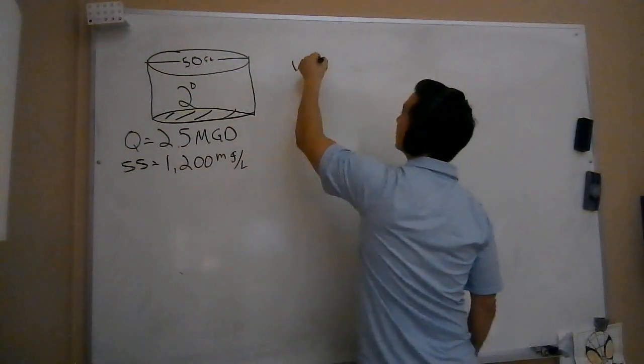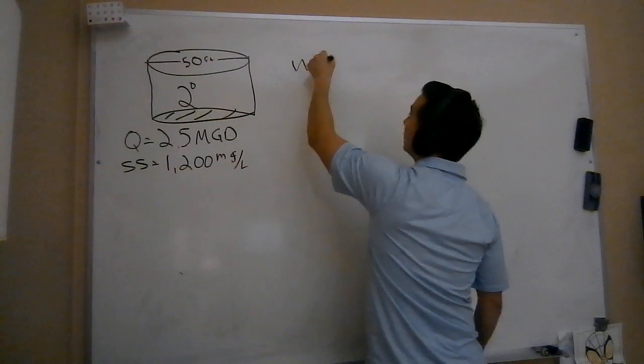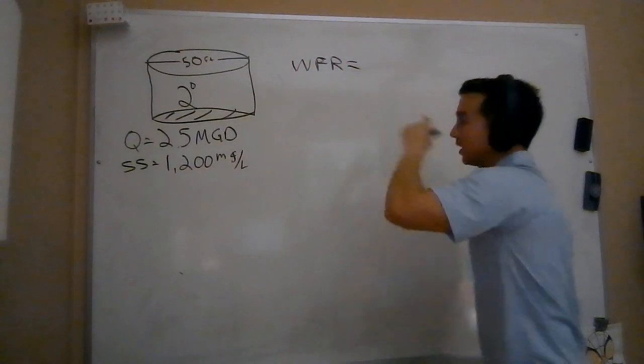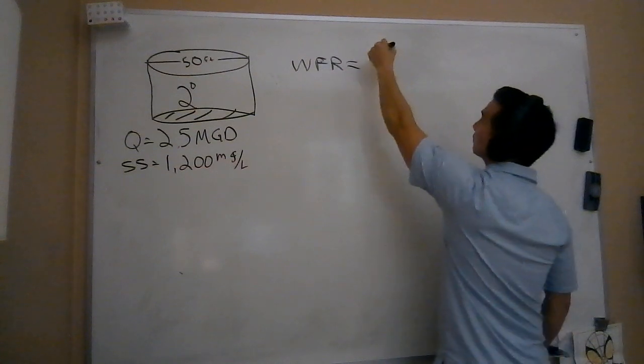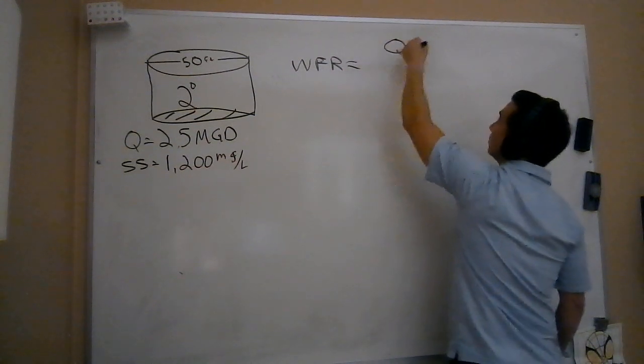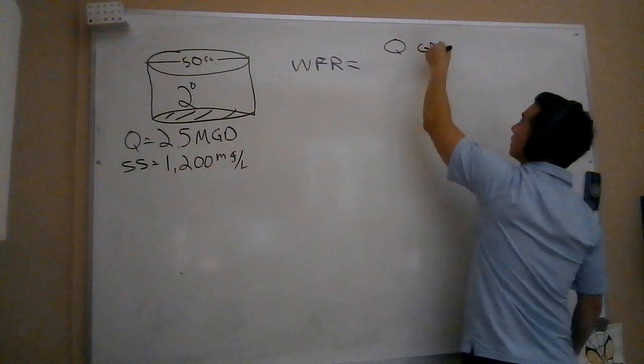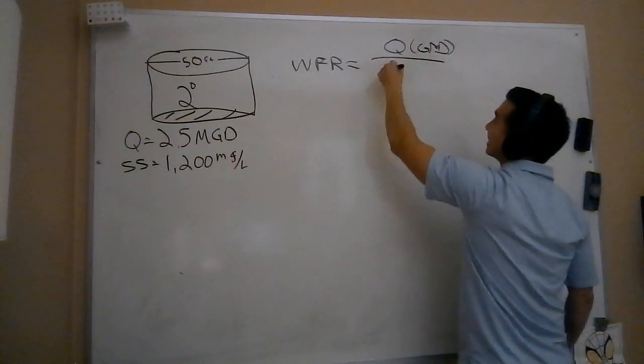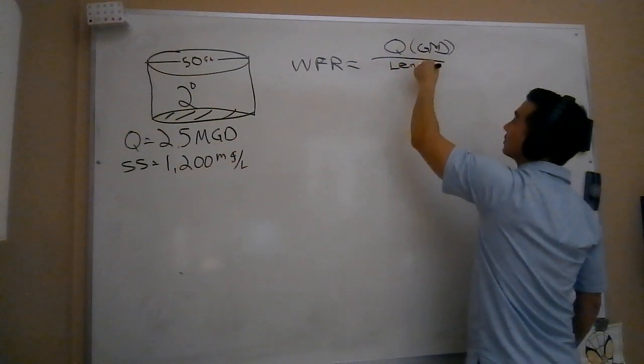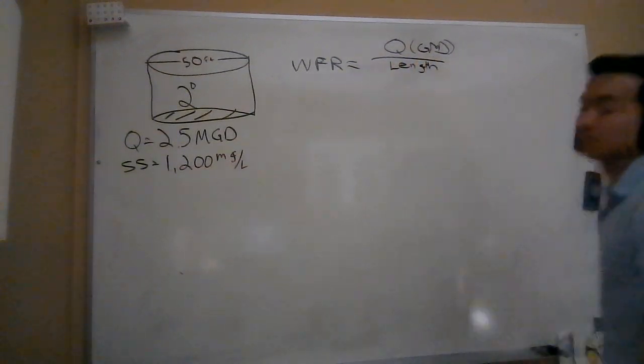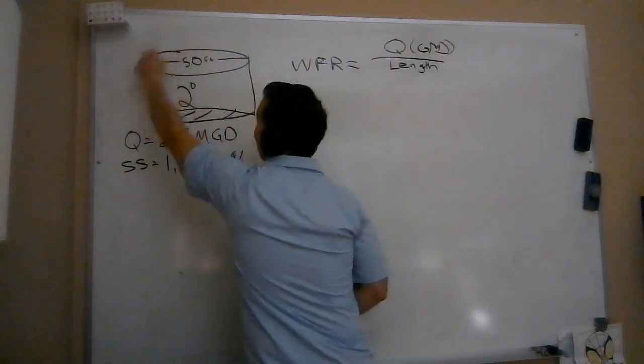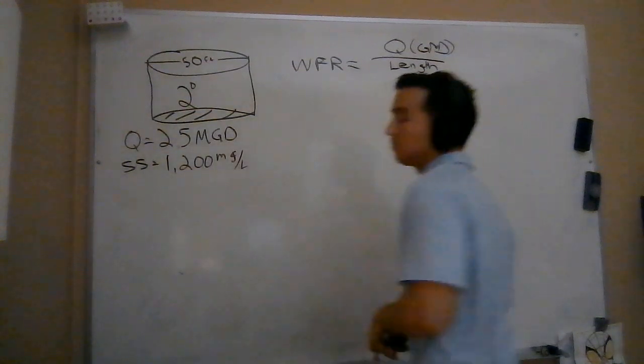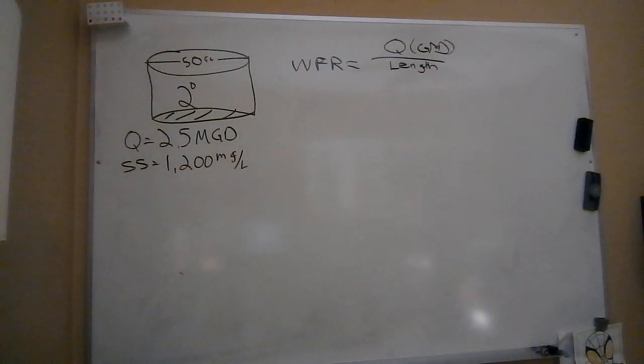We want to calculate our weir overflow rate, which I'm going to abbreviate as WFR. The formula for the weir overflow rate is Q in terms of gallons per day divided by the length of my weir. Notice a big difference between the weir overflow rate and the solids loading rate - we're not dividing by area, we're dividing by the length of the weir. That's going to be a different formula on that first page of our wastewater conversion sheet.